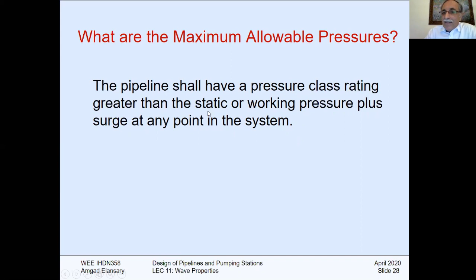For example, if my working pressure is 8 bar, and I know that with the increase of pressure it's another 2 bar, so it's 10, so I can use 10. So if it is working pressure 9, and then I have water hammer 2 bar, so it will be 11. I cannot use 10 bar. Do you understand that? So the maximum allowable pressure means that the class rating that you're going to choose for selecting the pipe must be greater than the static or the working pressure plus the surge pressure.